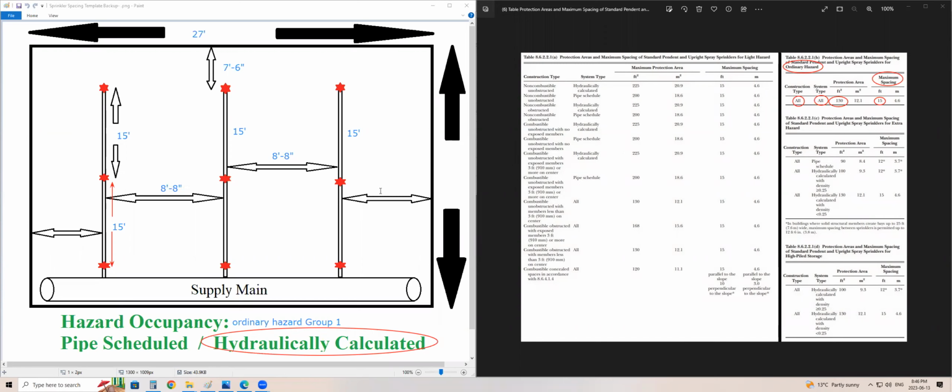And now that we've figured this out, I know I can be no greater than 4 foot, 4 inches because it's half of the maximum allowable distance. So if I'm 8'8" here, then off of the wall, I'm only allowed to be 4'4". So if we were to add all of this up, what do we got here? We've got 8, 8, 8, 8, 4, 4, 8, 16, 20, and it'll be the same because of the last one. So that would be 21'8" overall.